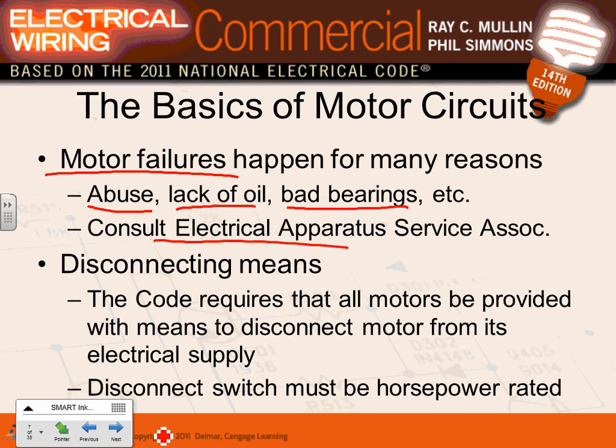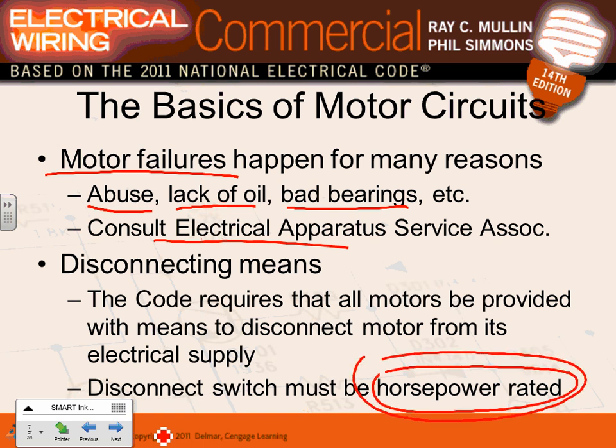Disconnect. When we have motors or any machine driven by a motor, the code requires you to have a disconnect. The disconnect has to be within sight of the motor or the machine, and the machine and the controller. You're going to see in a second. The disconnect must be horsepower rated. This is the most important thing about the motor. When we size disconnects, we didn't do it with you this quarter. We will be doing it next project. We will be sizing disconnects.